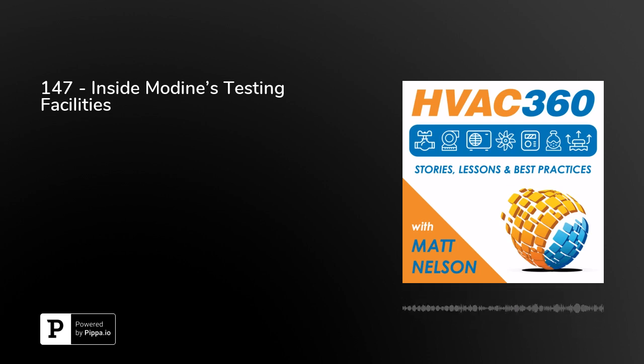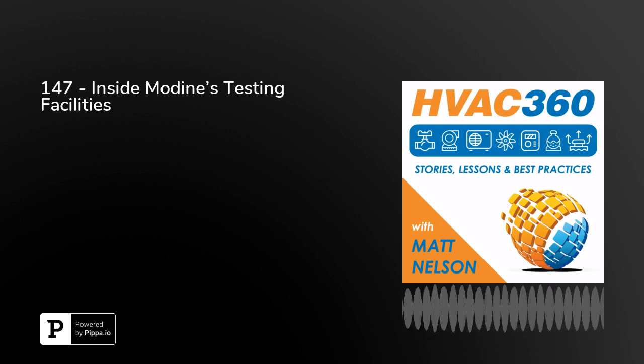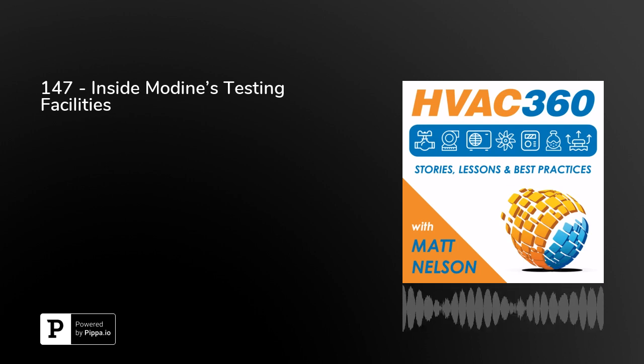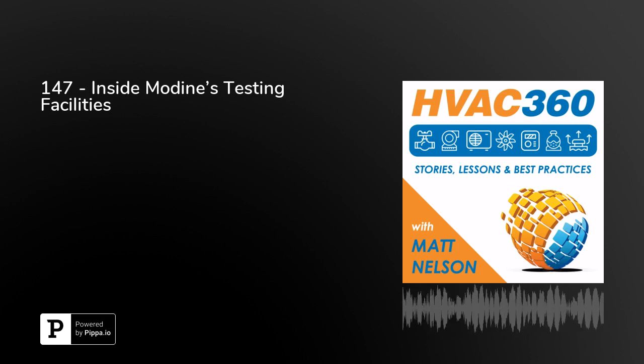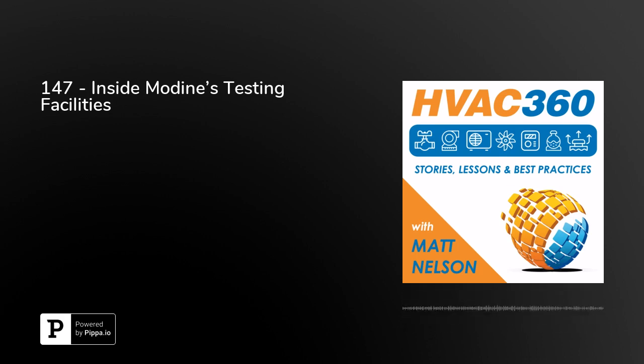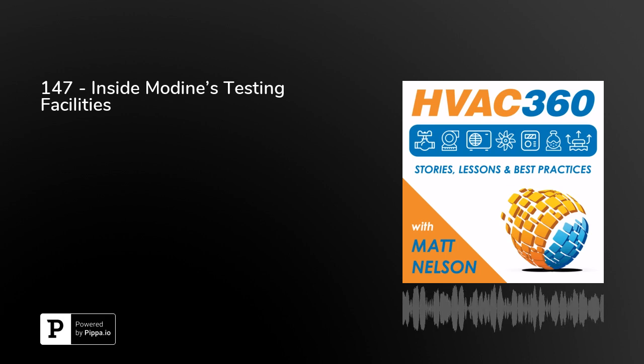On our heating products, the conditions for testing heating efficiency are pretty minor. Most heating equipment is generally tested at room temperature, 60 to 70 degrees. But particularly as we make high efficiency condensing furnaces for our outdoor rooftop units, we do a lot of testing at negative 30, negative 40 degrees to look at how those systems run in extreme cold environments. For example, for the dedicated outdoor air system, with 100% outside air coming across our heat exchangers, we make sure they function correctly at those extremely cold temperatures.